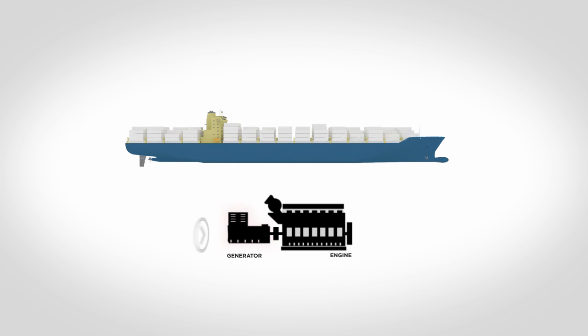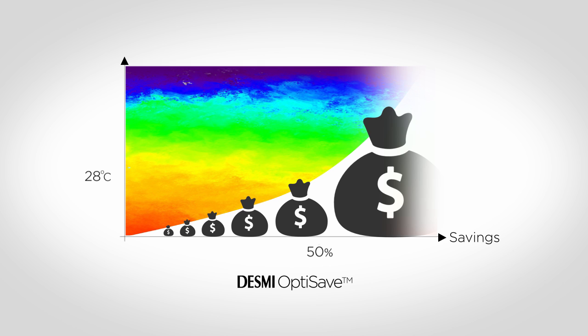By installing DESMI OptiSave energy saving system, you will be able to regulate the energy consumption according to actual cooling demand and thereby save fuel for your generating sets. You will achieve a 50% reduction in the energy consumption for your cooling water pumps already at 28 degrees seawater temperature. The power consumption of the pump will be reduced four times compared to the speed reduction of the pump.